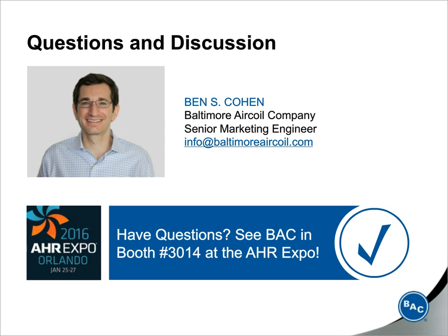So with that, Steve and I are going to answer some questions. We have a couple questions on which is more efficient, an open tower or a closed circuit cooling tower. The general answer is that open cooling towers have about twice the capacity of a closed circuit cooling tower at a given horsepower. However, when making those comparisons, you really need to compare the closed circuit cooling tower to an open circuit tower with a heat exchanger. Then, when considering installation costs and flexibility, closed circuit cooling towers really provide an excellent option to increase reliability and ensure good performance.